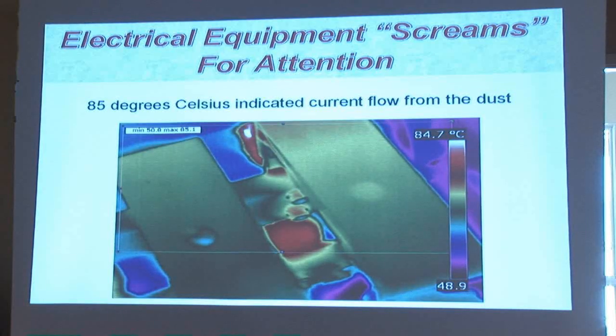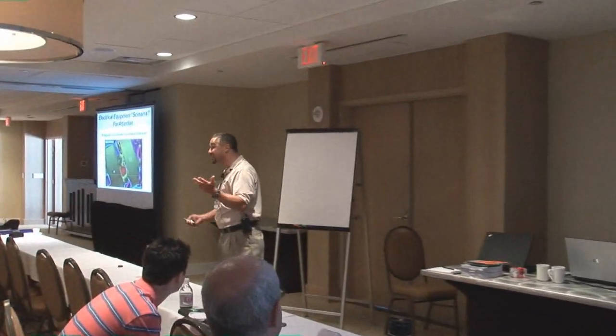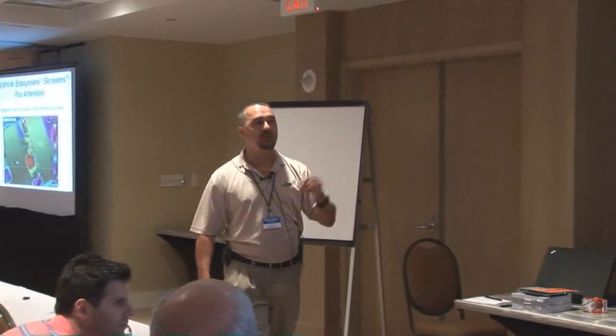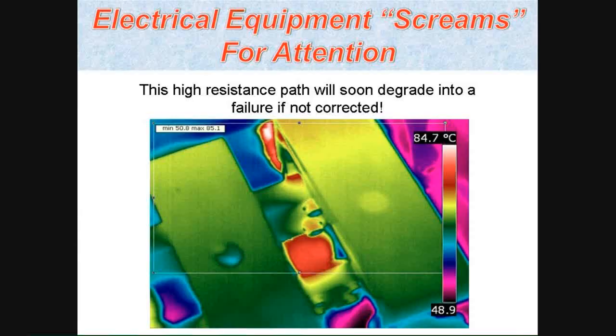By the way, we can't see the direct source of where this is coming from. So is that temperature true? No, I guarantee it's higher at the source. So it's at least 85 degrees Celsius, meaning we've got a high resistance path there. It's going to fail. There's no doubt in my mind, and there was no doubt in Gavin's mind.